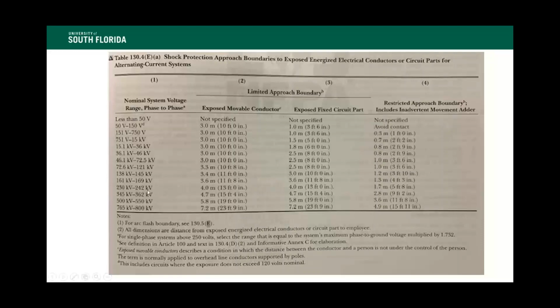Now, if we go to the other extreme at the very bottom of the list, we see the 765,000 volts to the 800,000 volt range. And we see greater limited approach boundaries of 23 feet 9 inches for both the exposed fixed circuit part as well as the movable conductor. And we see 15 feet as a restricted approach boundary. So this is a very important table, again based on voltages, to establish our shock protection approach boundary.